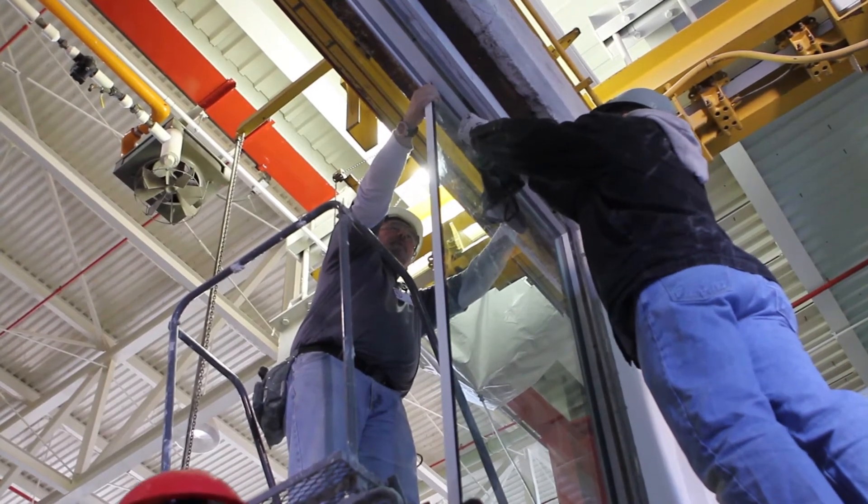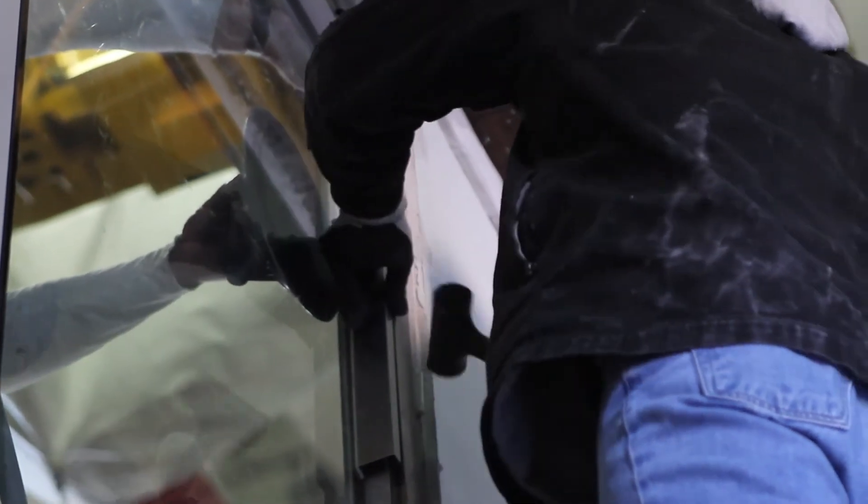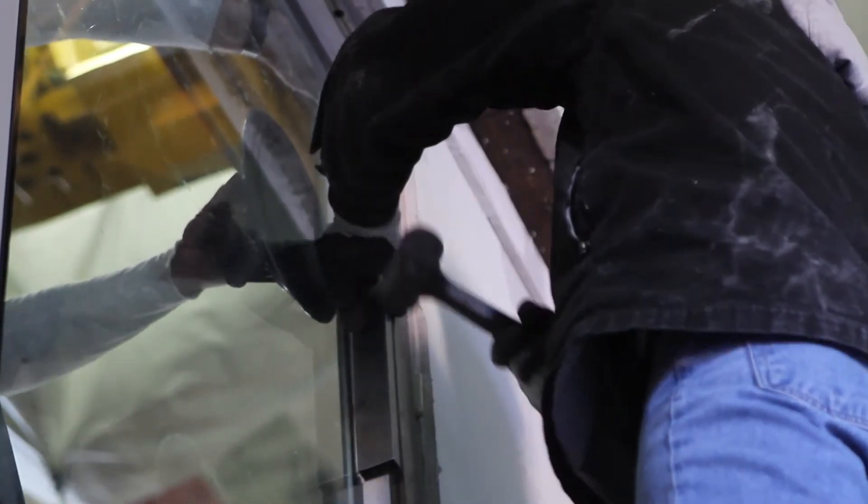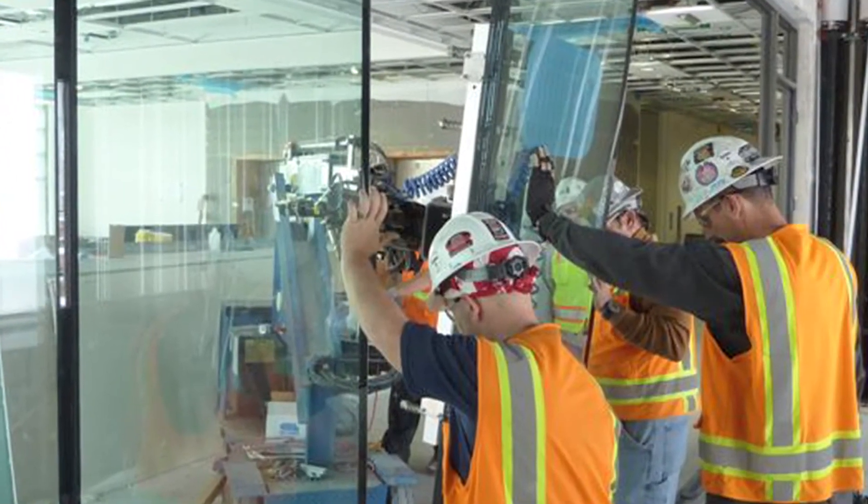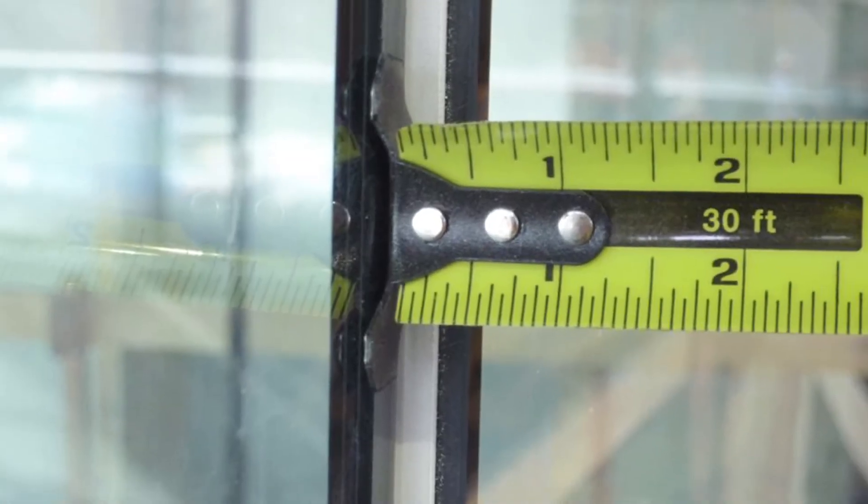Secure the pane temporarily with short glass beads. Repeat these steps for the remaining panes of glass, ensuring that all panes are in proper alignment. Also ensure that all intumescent tape surfaces at the butt joints are in complete contact.